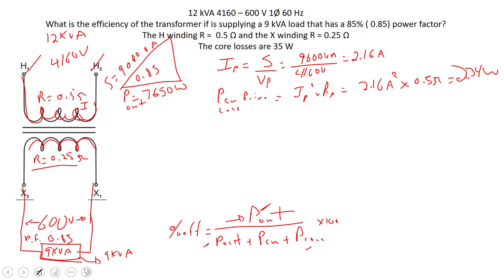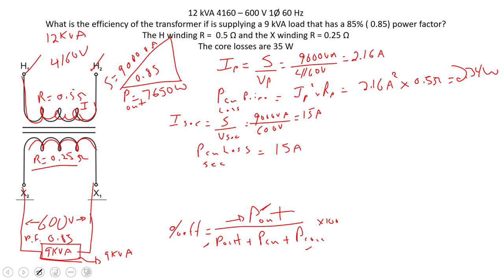For the secondary: I secondary equals S divided by V secondary, so 9000 VA divided by 600 volts equals 15 amps. The copper loss on the secondary is I squared R: 15 squared times 0.25 ohms equals 56.25 watts. Now we have both copper losses calculated.